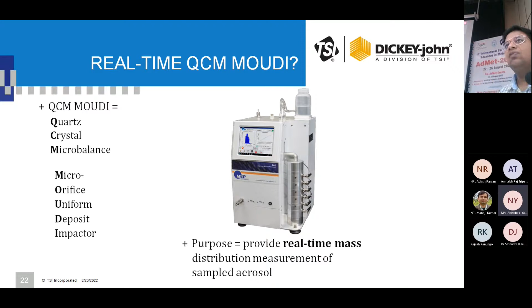We will have all the data at one particular humidity. In this instrument, we have 6 channels. It's basically a cascade impactor, but in each stage we have installed a quartz crystal. So how it happens is, the quartz crystal also acts as an impaction plate. When the aerosol comes in, some of the aerosol, depending on its size, settles over the quartz plate, and the rest goes on to the next plate. On the top we have bigger size particles, and on the bottom we have smaller size particles.